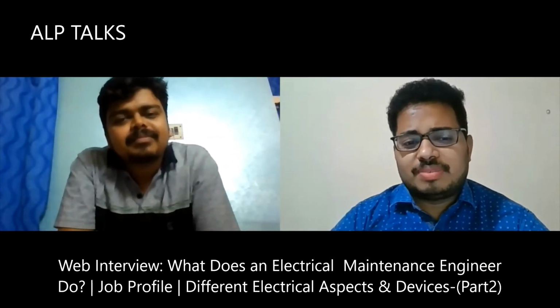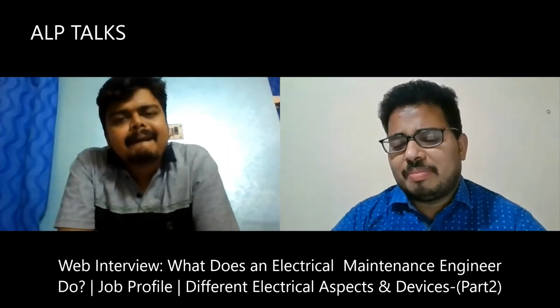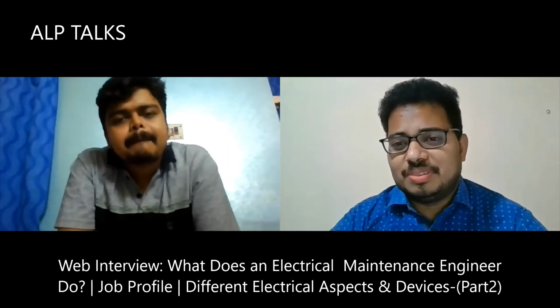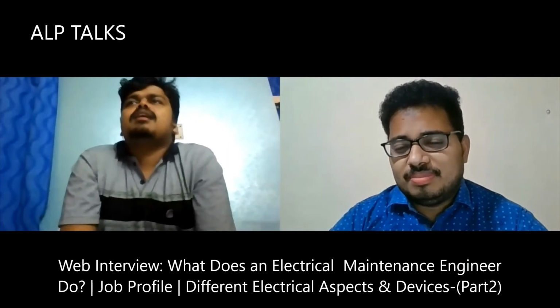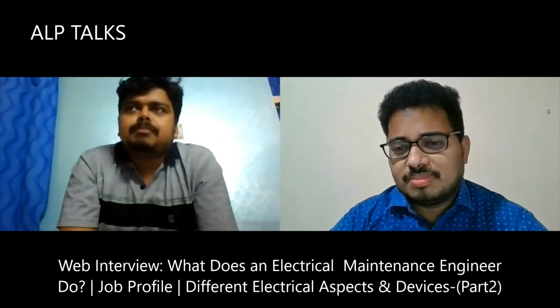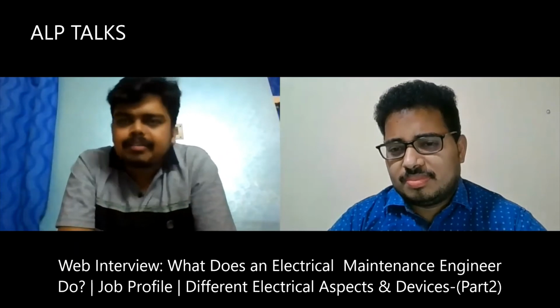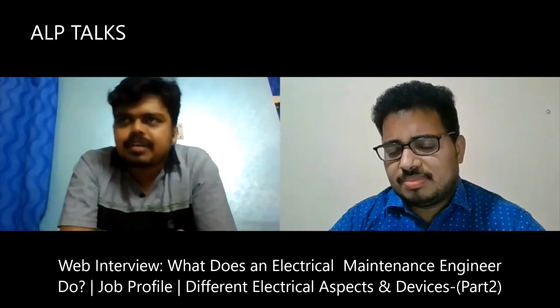So for circuit breaker or HT panel maintenance, generally what we will do - in ACB circuit breaker, you have to just rack it out after isolation, tag everything, and maintain after the power isolation.